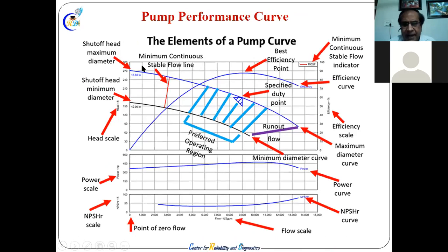You cannot go outside the efficiency zone, then again it will be an energy issue. So we have to think about that. Which is the minimum diameter I will keep, because on this power scale you can see the power is almost the same going on. So I must get maximum efficiency with the minimum power. This is the power, and NPSH, this is the curve. Net positive suction head, we'll discuss a little bit later.